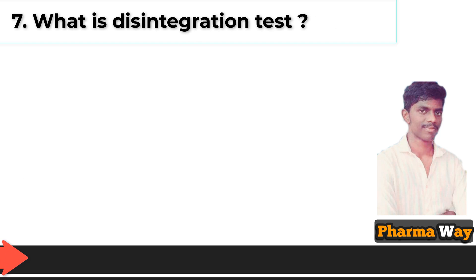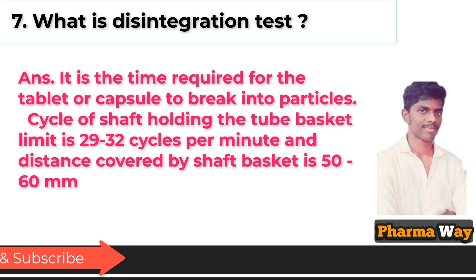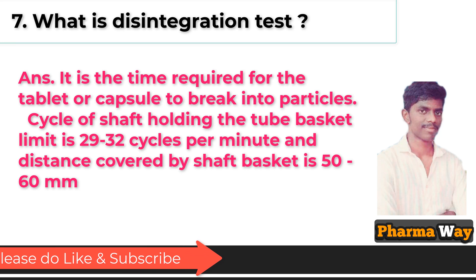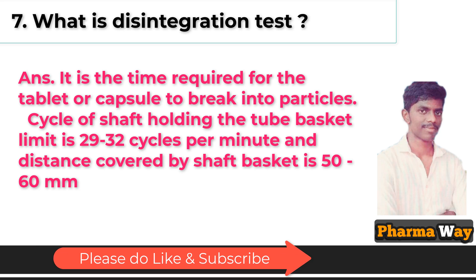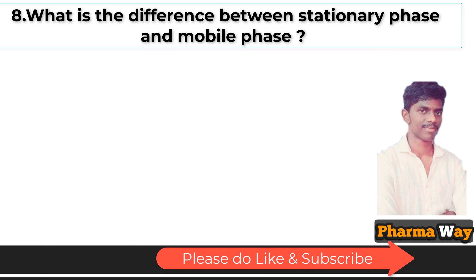What is the disintegration test? Answer: It is the time required for the tablet or capsule to break into particles. The cycle of the shaft holding the tube basket is 29 to 32 cycles per minute, and the distance covered by the shaft basket is 50 to 60 mm.